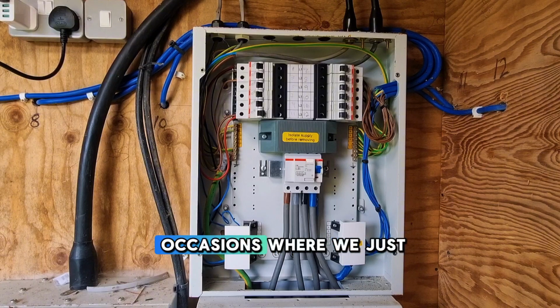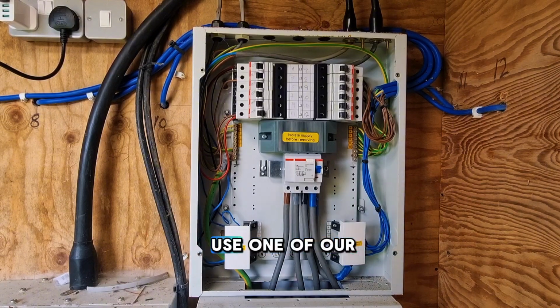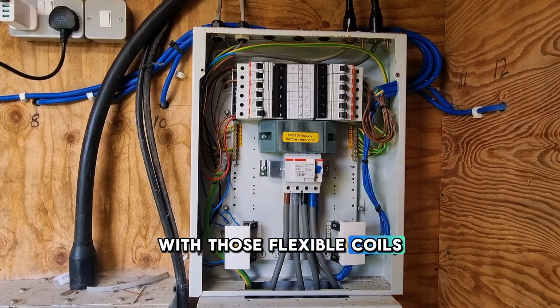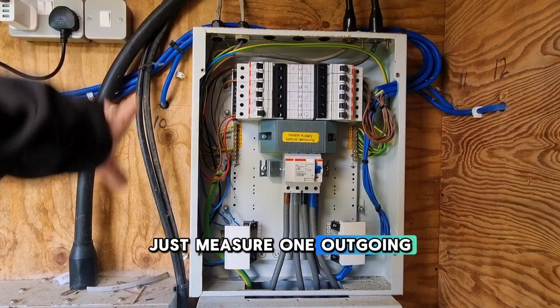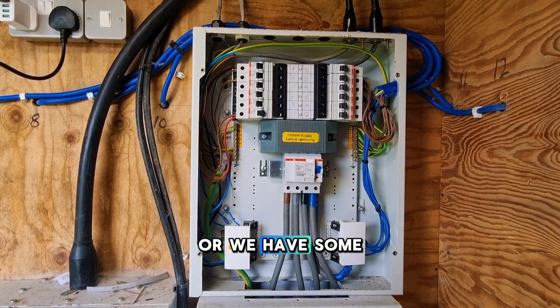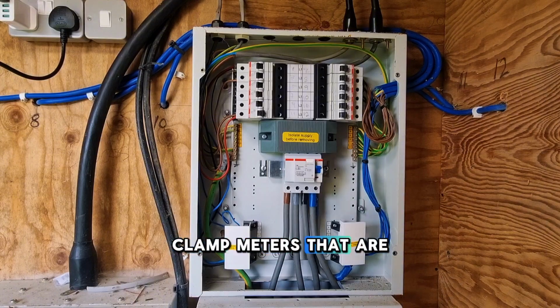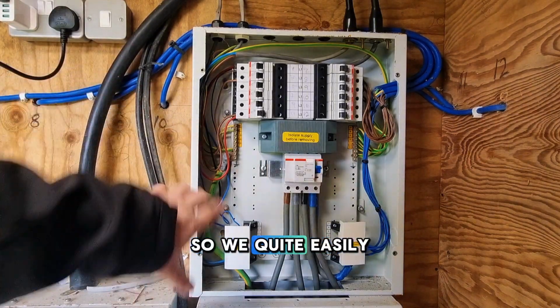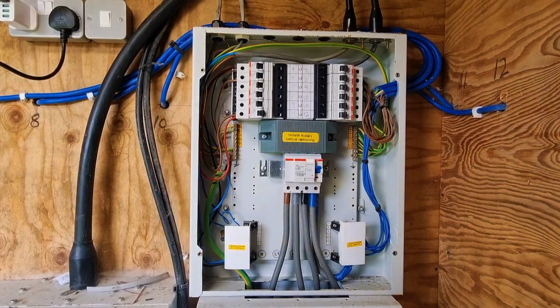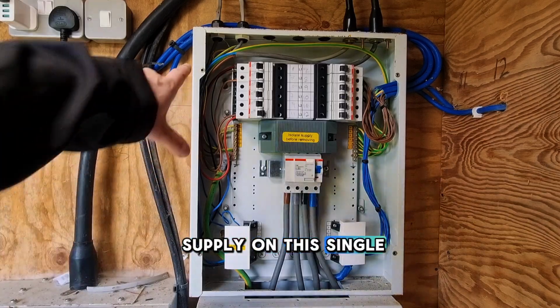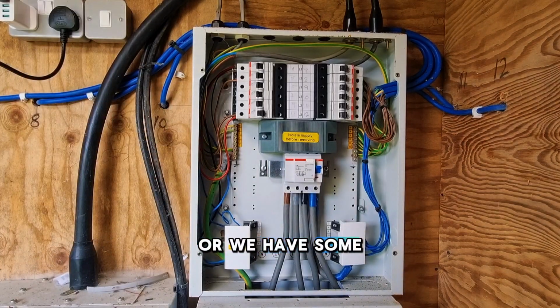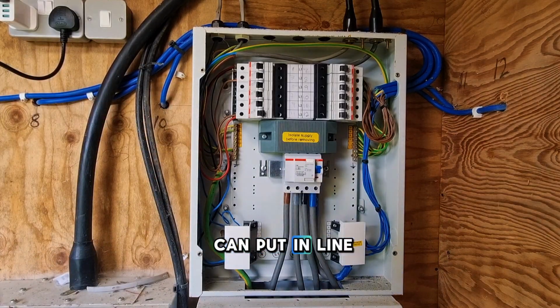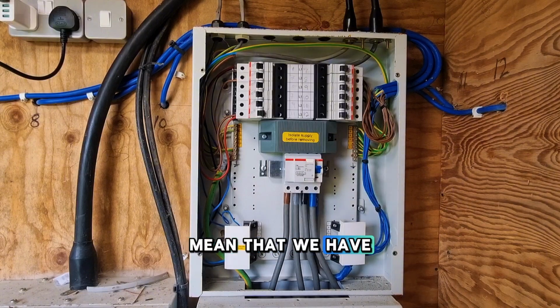There are a lot of occasions where we just want to monitor one outgoing circuit from a distribution board. We can either use one of our 3-phase loggers with flexible coils to measure one outgoing set of cables, or we have single clamp meters able to fit within the panel, logging the outgoing supply on this single circuit. We also have other tools that fit in line, which would mean making a small adaptation to the board to take that measurement.